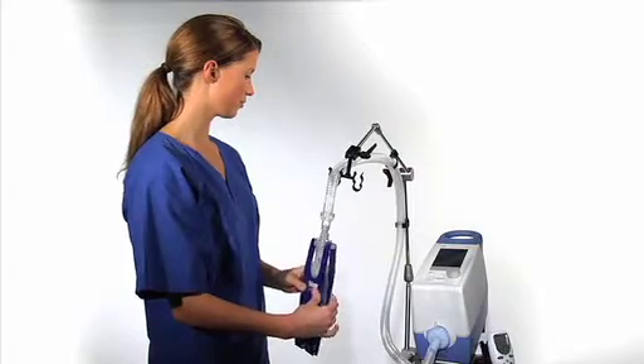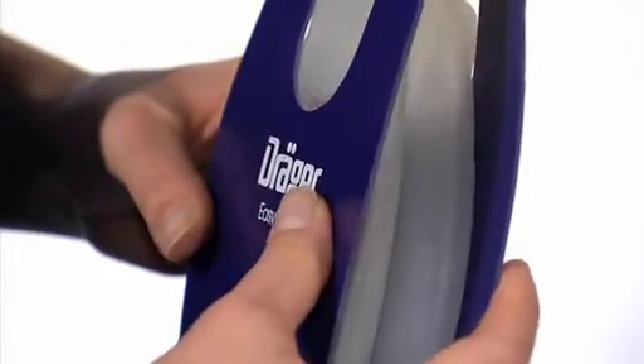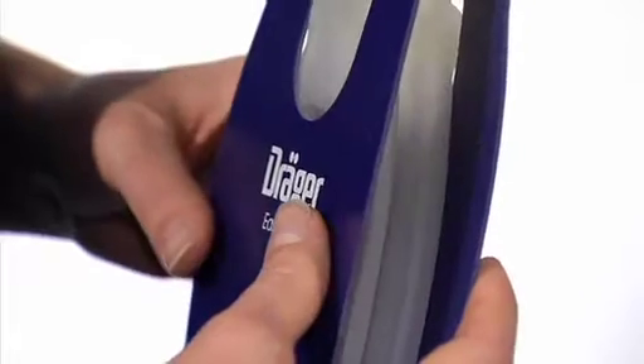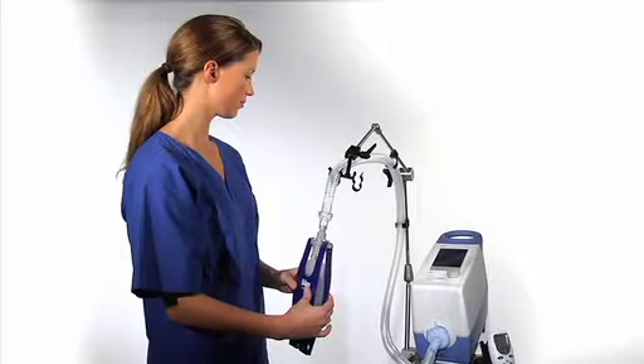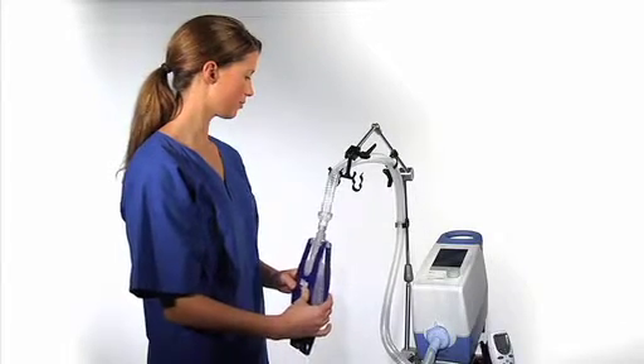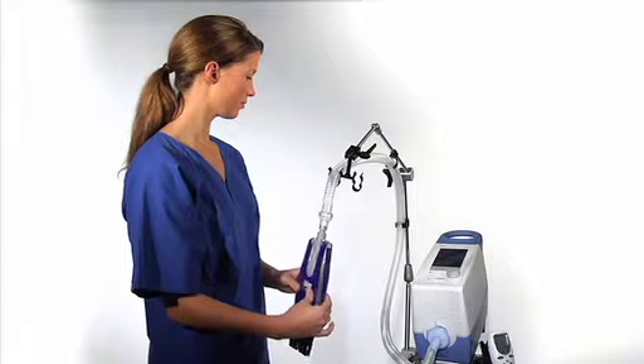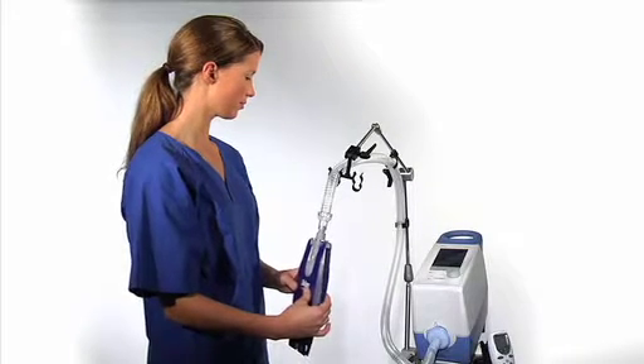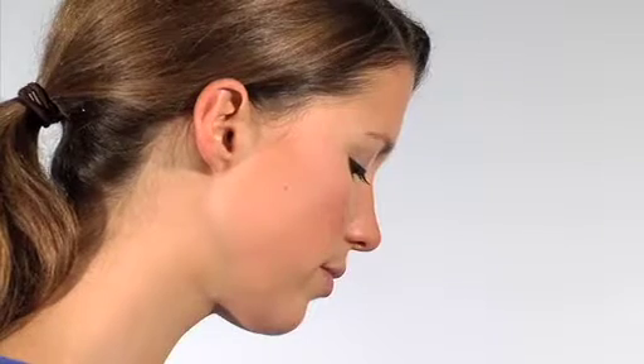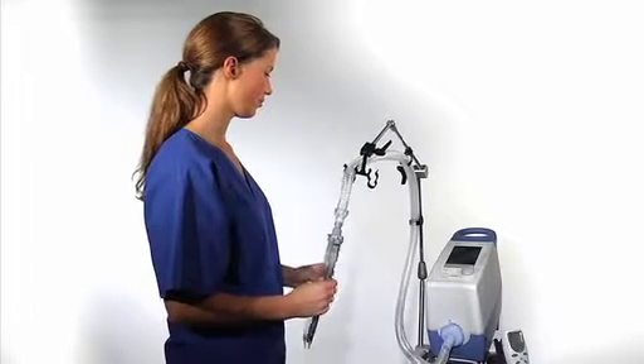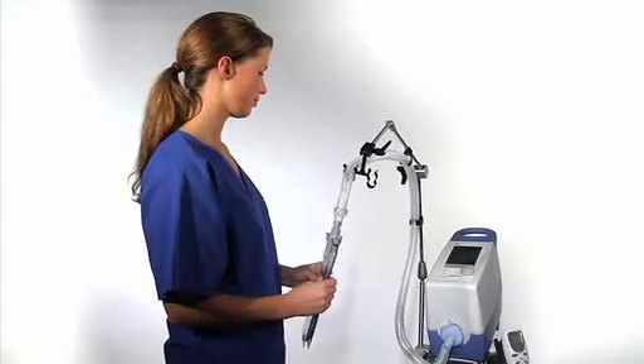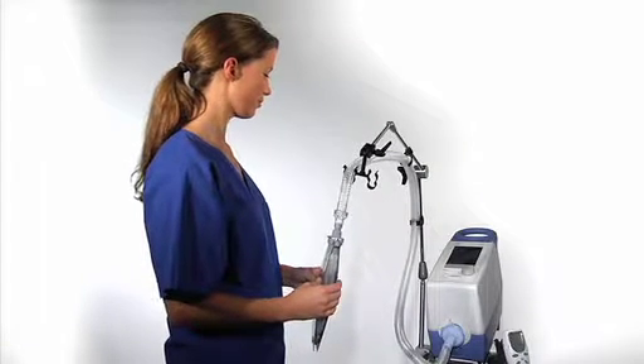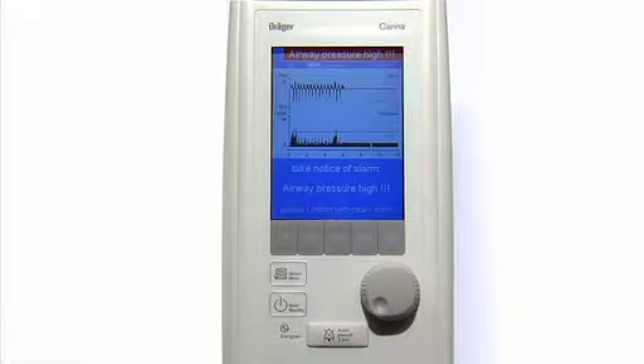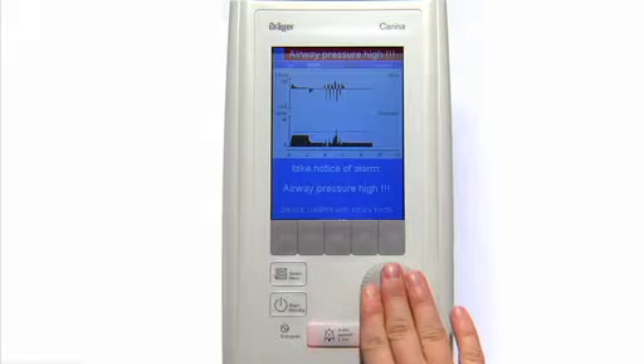Each time it's compressed, expiration is possible. We call this free breathing. If the patient wishes to exhale, this is possible. This functionality is available for every mode of ventilation. Please compress the test lung several times during the upper pressure level. After a few seconds of compressions, you will hear an alarm signal and the message "Airway pressure high" will appear. Please confirm the alarm by using the rotary knob.